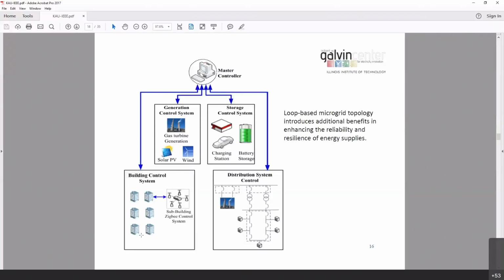Individual buildings are managed by a building energy management system manufactured by Siemens, covering all 52 buildings, which provide the daily load profile to the master controller. You also get data from individual generators, from the batteries, and from the campus grid. All that information goes into the loop-based microgrid's master controller, which is basically software located at our center.